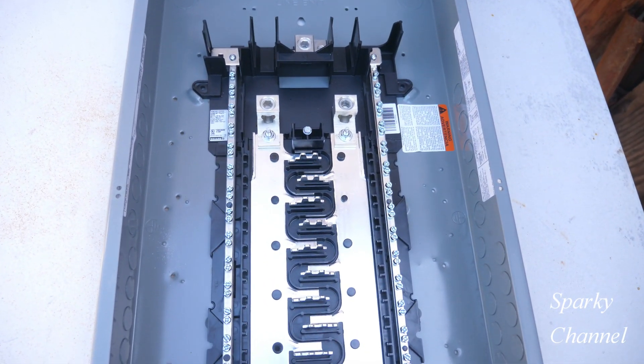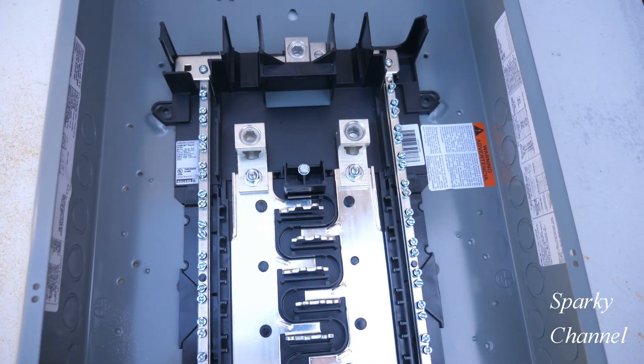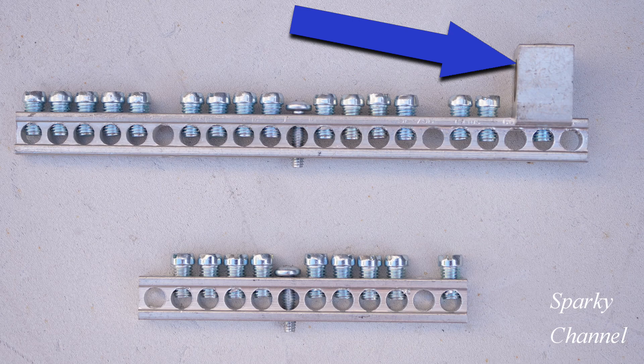Hi, this is Bill for Sparky Channel. This is a Homeline load center. This load center can be used as a sub panel but can be converted to a main panel by adding a main breaker — therefore it's called convertible. My topic today is going to be how ground bars are installed in Homeline panels. These are the ground bars that come uninstalled with this load center. This one has nine terminals and this one has 15 terminals, plus an included lug terminal in case you would like to convert this panel to a main panel.